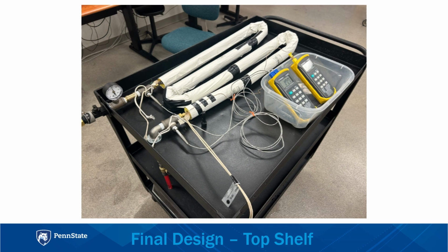This shows a close-up view of the top shelf of the cart, where the water enters through the inlet with the pressure gauges into the orifice and through the copper tubing, which is wrapped with heating tape and covered in insulation. There are two thermocouples, one at the inlet and one at the outlet, and a third thermocouple inside the insulation within the heating tape to measure the temperatures of the inlet water, outlet water, and the surface temperature of the tape.